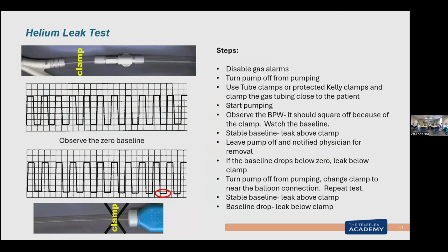To do this test, we turn off the alarm, because I'm going to make an alarm when I do this. I get a pair of hemostats and clamp on the tubing as close as I can to the patient. So now I've isolated the balloon and I'm monitoring anything from the pump up to this point. I turn the pump on and I watch this. Now I'm going to get a high pressure line because this is squaring off at 250. That's because I clamped. Perfect. I know that. But what I'm watching is this, because that's where I'm looking for this possible helium loss.